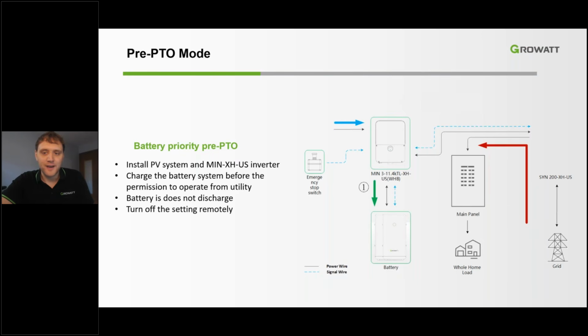Another great feature of the MIN inverter is the Pre PTO function. The Pre PTO function is used to allow the inverter and battery system to be installed before the interconnection approval is granted by the utility. In the Pre PTO mode, the battery is charged with solar energy and does not discharge until the setting is turned off. This feature allows the battery to be fully charged for when the permission to operate is granted from the utility, and enables the technician to be sure that everything is in good working order and ready to begin operation.